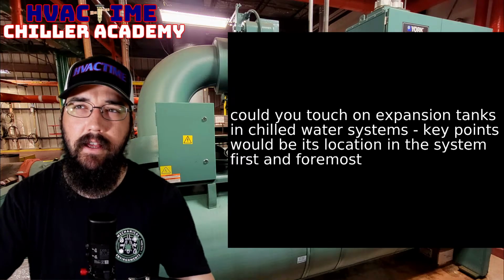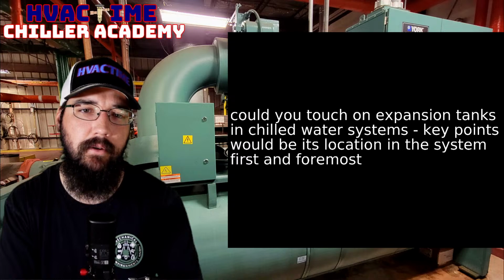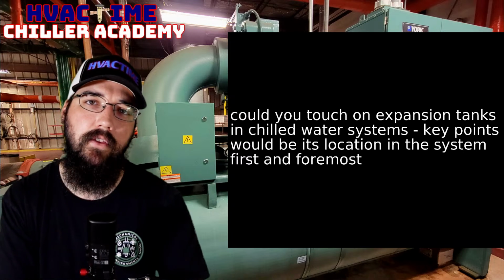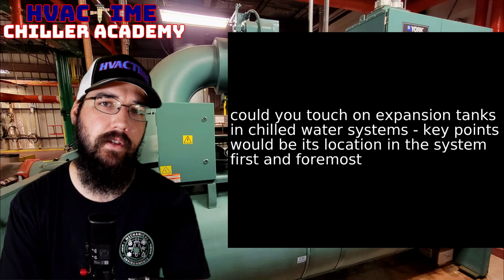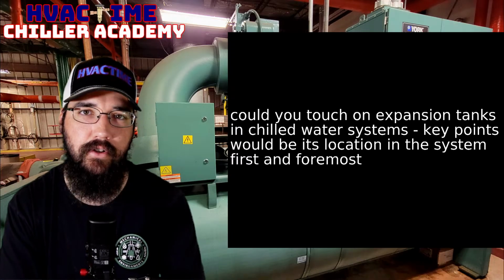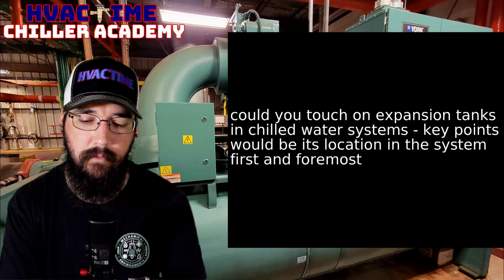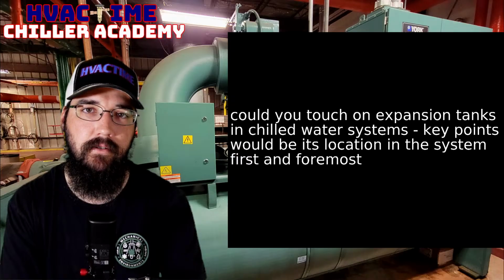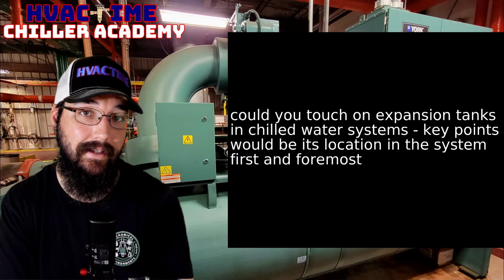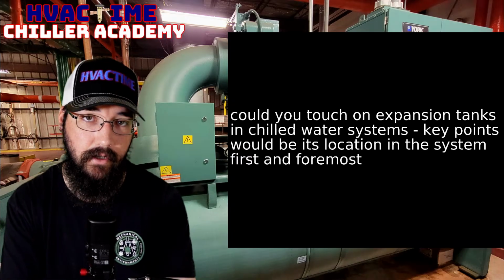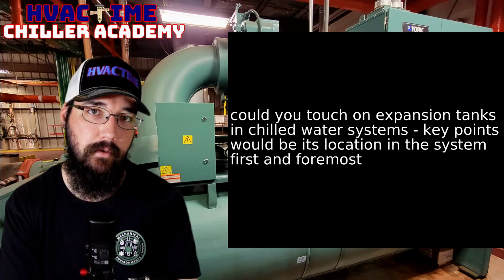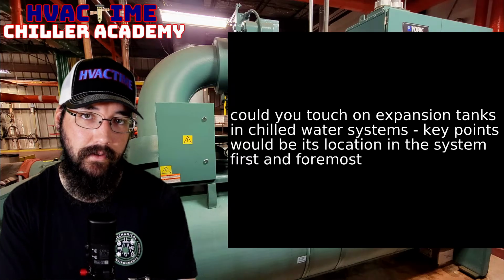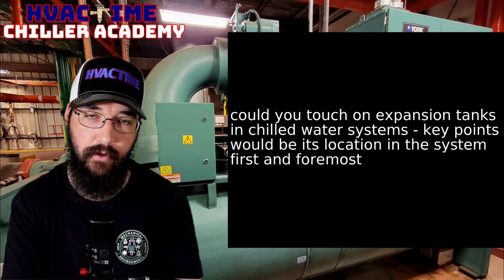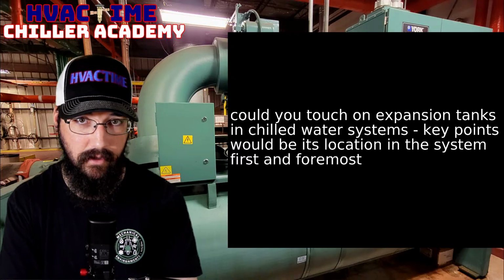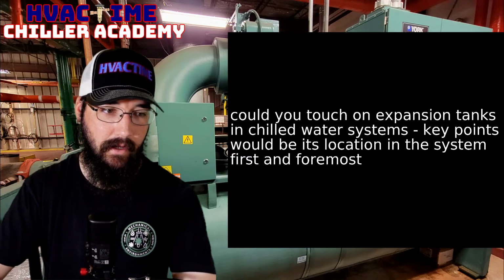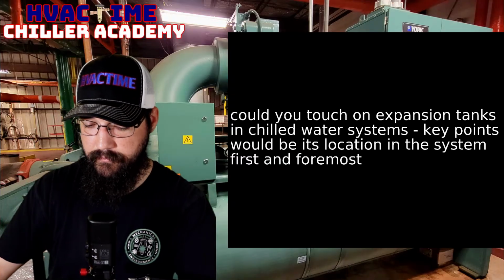And I've heard some guys say you want your tank pressure slightly more than the loop pressure. I hear some say slightly less. I personally just kind of shoot for a median. If I'm looking for a 30 psi loop pressure where my tank is specifically, so that your elevation changes are accounted for, so if I'm looking at 30 psi there where it's connected to the pipe, then I want to see 30 psi on my tank, give or take a couple of psi. So it doesn't have to be absolutely perfect.